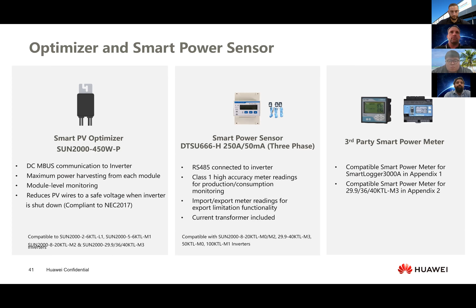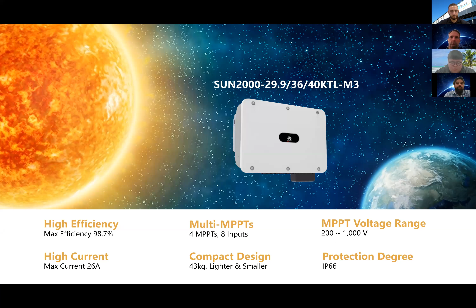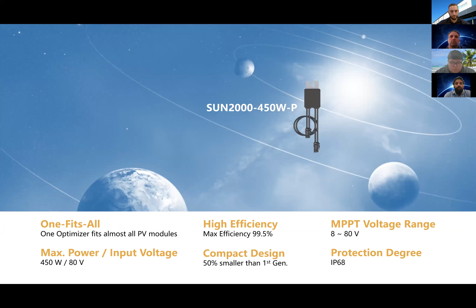Again, 29.9, 36, 40 M3, 4 MPPTs, 8 inputs, much lighter, 43 kilo, higher efficiency. So the input current has gone from 22 amps to 26 amps. Now this is becoming very standard now. We all know the reason. Bifacial modules might be used more and more. MPPT voltage range, 200 to 1000 volt. The sweet spot, if you want to get this full efficiency, is somewhere around 480 to 850 volts. Optimizers, 8 to 80 volts, so can be used with larger panels as well.